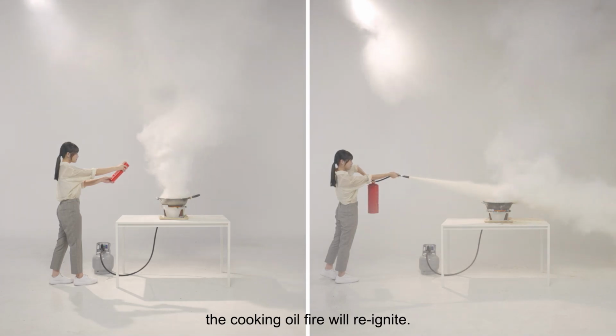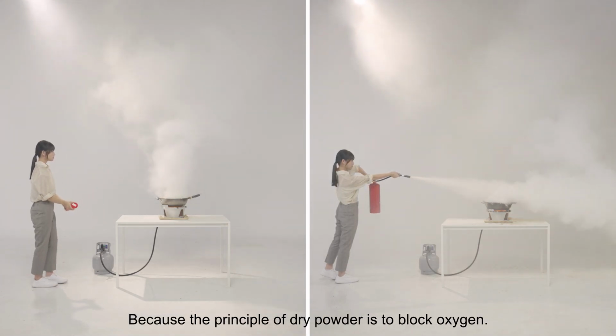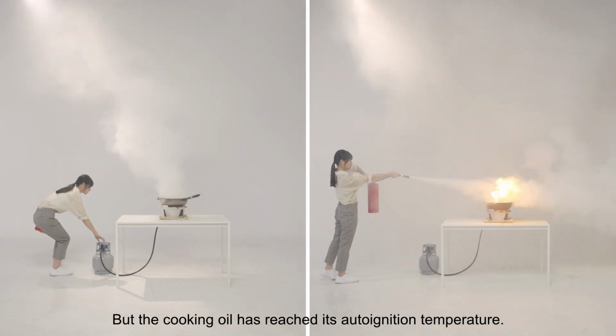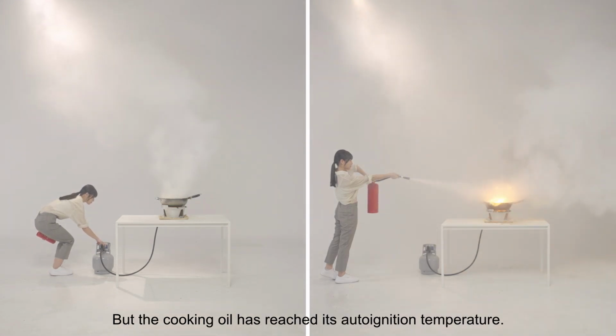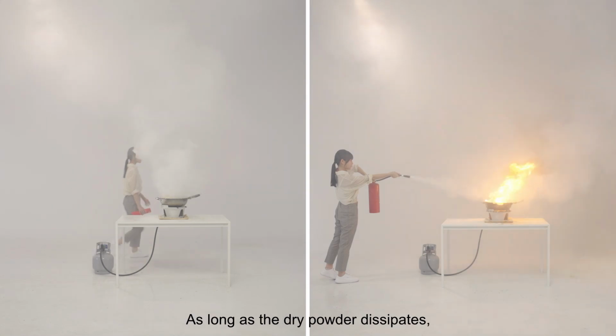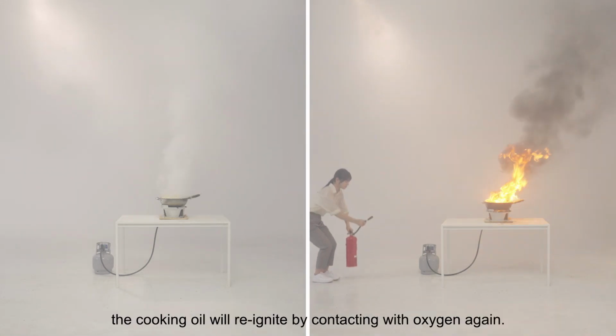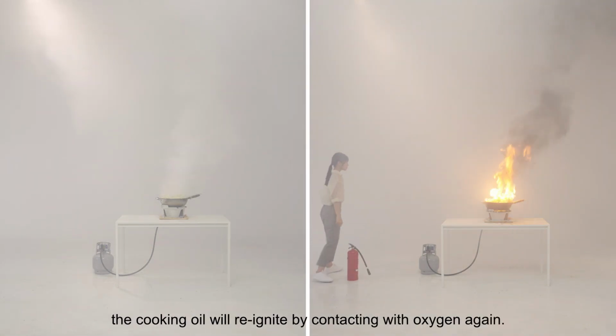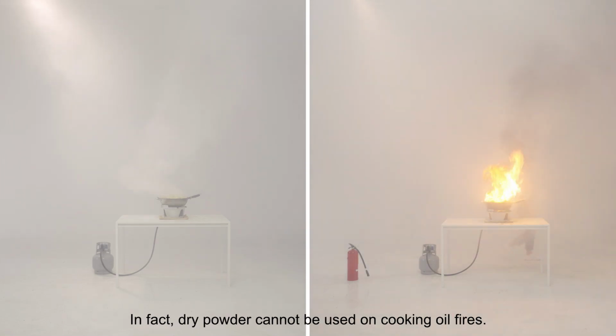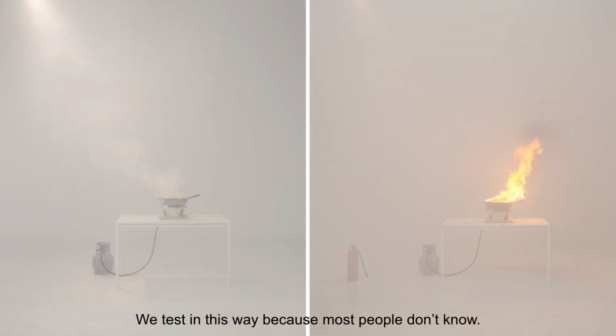The dry powder on the right screen, regardless of whether it sprays intermittently or continuously, the cooking oil fire will reignite, because the principle of dry powder is to block oxygen, but the cooking oil has reached its auto ignition temperature. As long as the dry powder dissipates, the cooking oil will reignite by contacting with oxygen again. In fact, dry powder cannot be used on cooking oil fires. We test in this way because most people don't know.